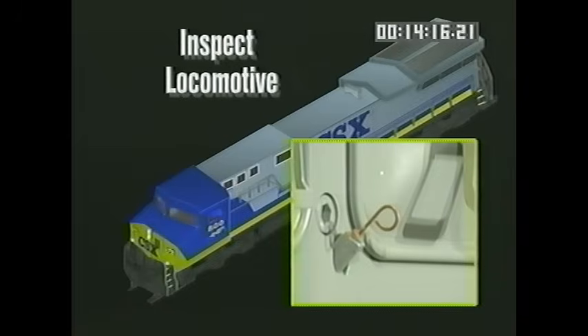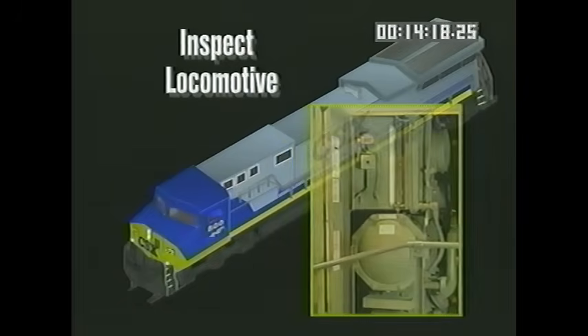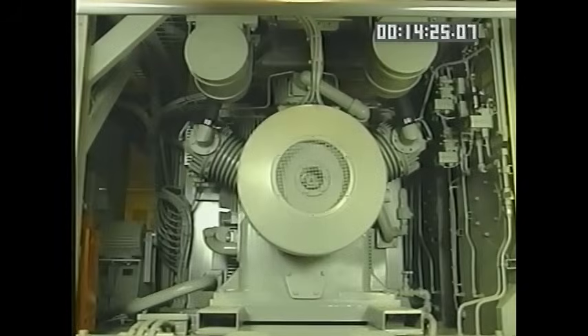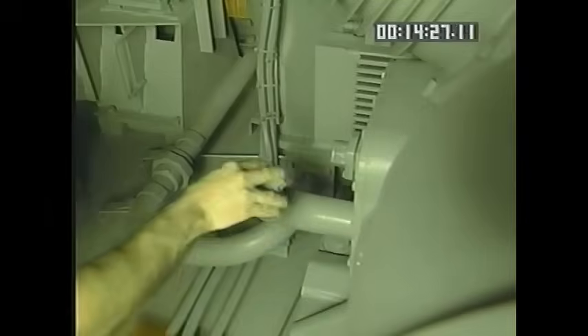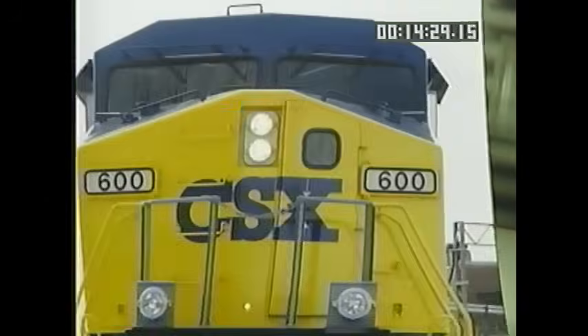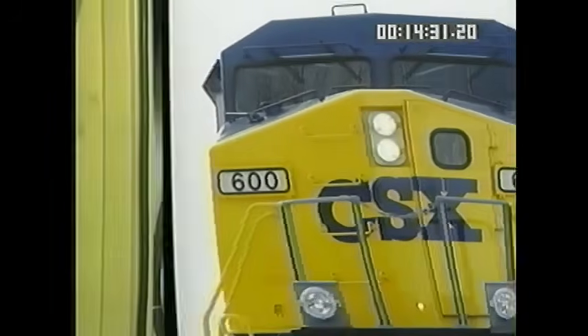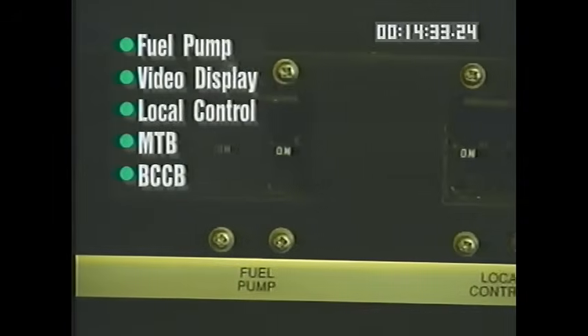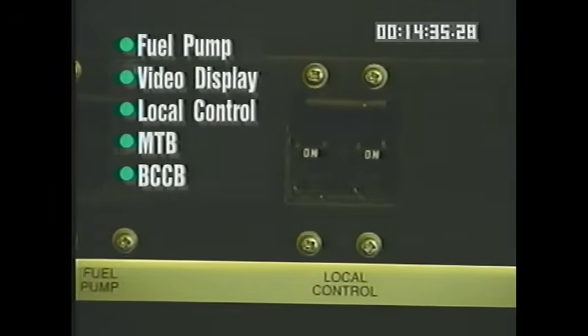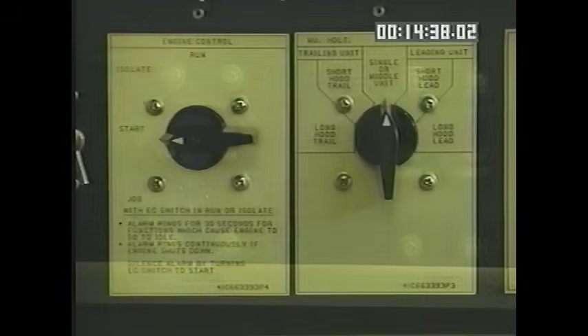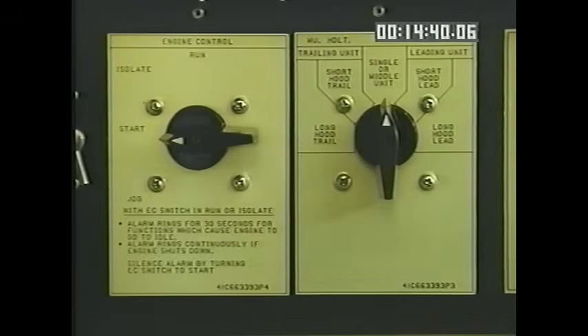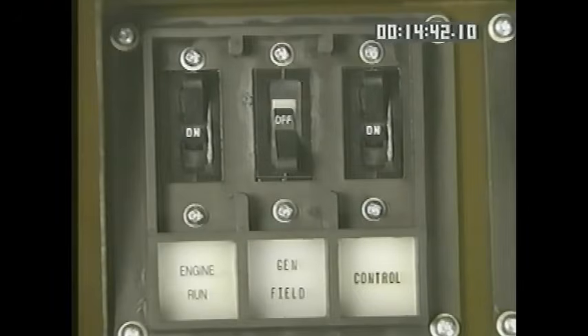Verify that the crankcase is serviced with lubricating oil. Ensure that the cooling water is at the proper level by checking the sight glass. The air compressor oil level should be near the top of the fill. In the operator's cab, close the battery switch. Turn on the appropriate circuit breakers on the EC panel. The engine control switch should be in the start position. On the operator's console, turn on the appropriate breakers.